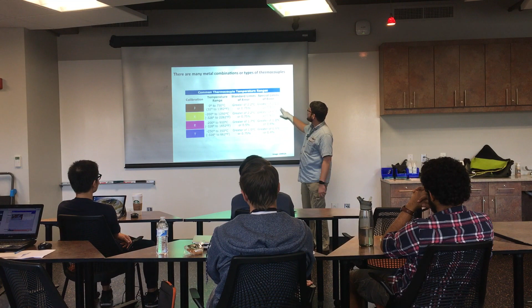So these are some of the different thermocouples that are out there. There's lots, but J, K, E, and T thermocouples are some of the more common. K has a very wide temperature range, so -200 to 1250 C. But you can see, in the best case, the limits of error are 1.1C or 0.4%. Standard, so 2.2C. So maybe not super great, but they're cheap. For smaller ranges like a T-type, you can get down to ½ degree C or so. And the only difference between those is the different kinds of metals that are used in them.